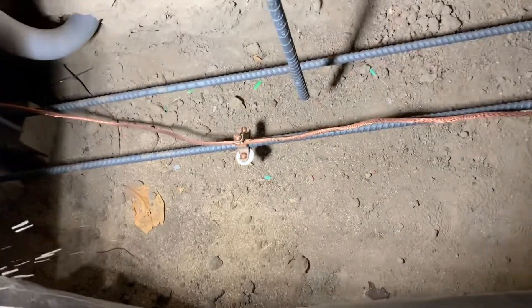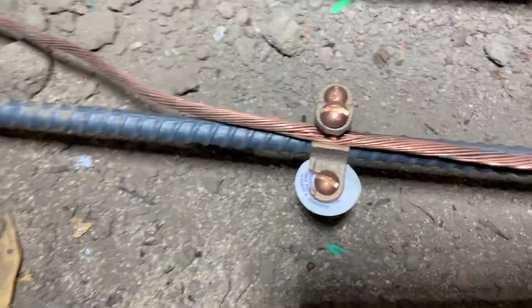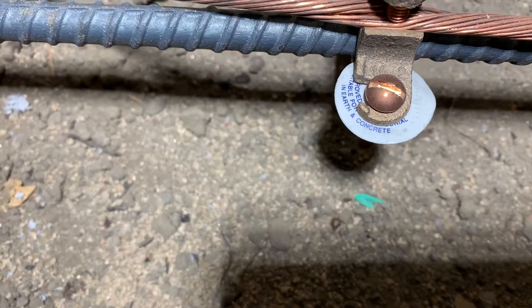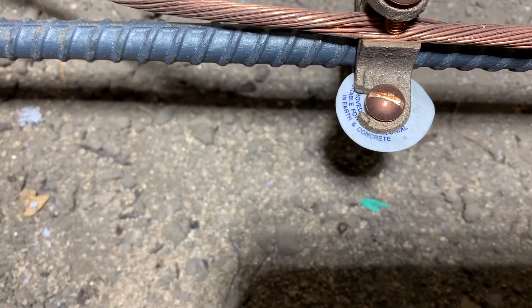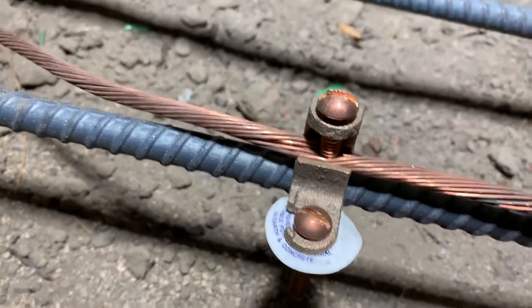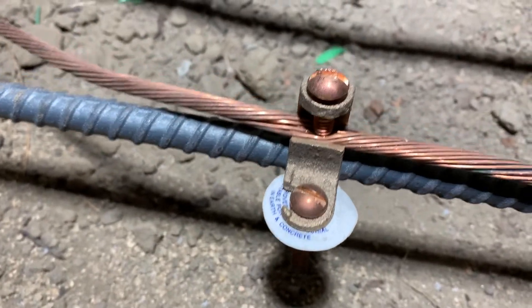I'm going to get this label for you to see. Not sure if that's typical for you to see, but it's nice in there. You can see that it's rated for in-ground concrete, direct burial, lay-in lug style clamp.